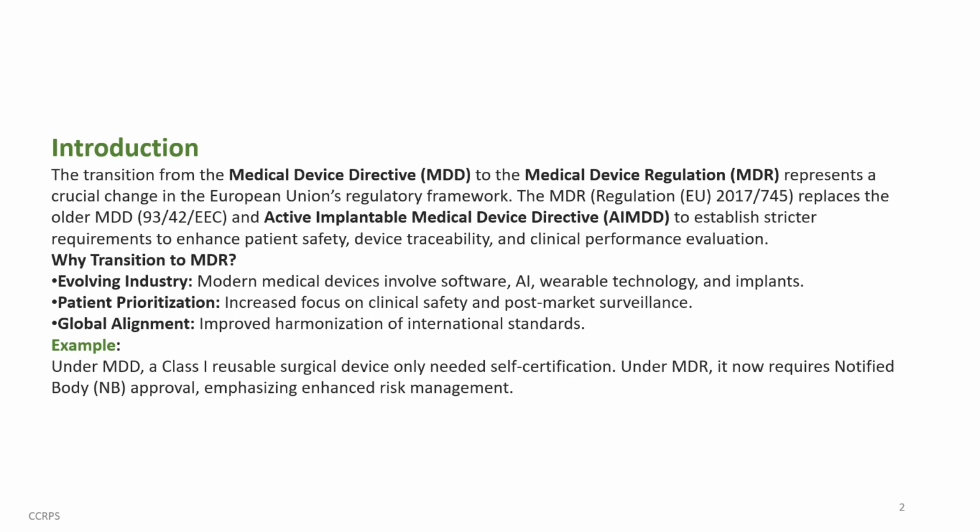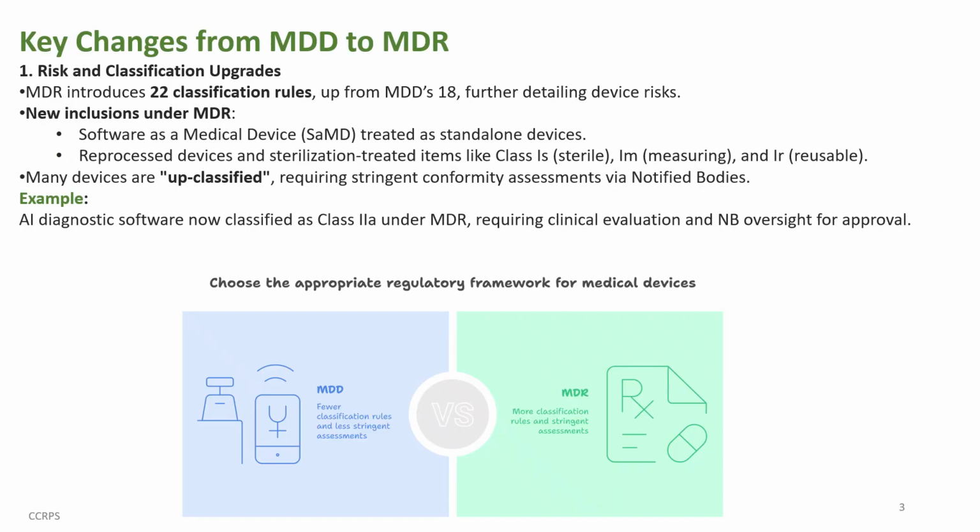Why transition to MDR? Evolving industry: modern medical devices involve software, AI, wearable technology, and implants. Patient prioritization: increased focus on clinical safety and post-market surveillance. Global alignment: improved harmonization of international standards. Under MDD, a Class 1 reusable surgical device only needed self-certification. Under MDR, it now requires notified body approval, emphasizing enhanced risk management.